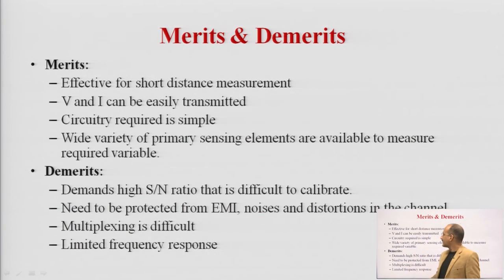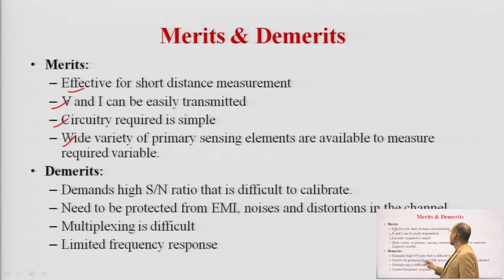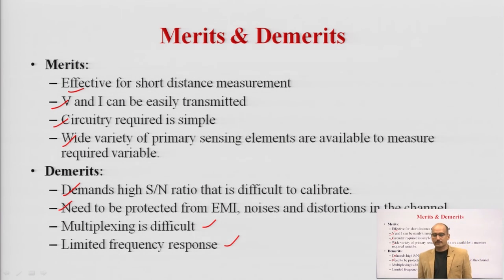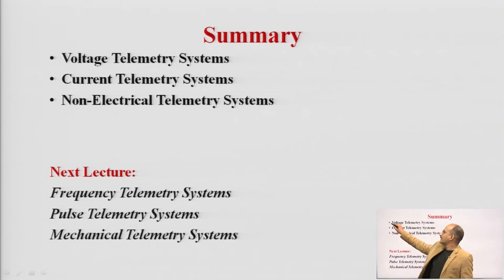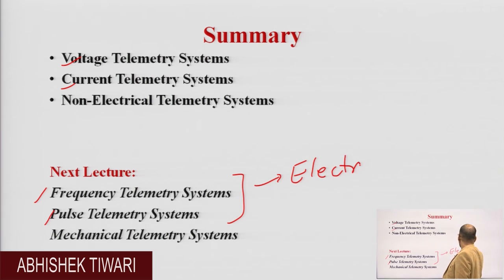The merits and demerits of voltage and current telemetry systems are: both systems are effective for short distances only; voltage and current signals can be easily transmitted; circuitry required is simple; and a wide variety of primary sensing elements can be used. However, demerits include: they demand a high signal-to-noise ratio (SNR); they need to be protected from electromagnetic interference (EMI) and other noise; multiplexing is not available or very difficult; and there is limited frequency response. In the next part, we will study frequency telemetry systems and pulse telemetry systems, both of which also belong to the electrical telemetry system.